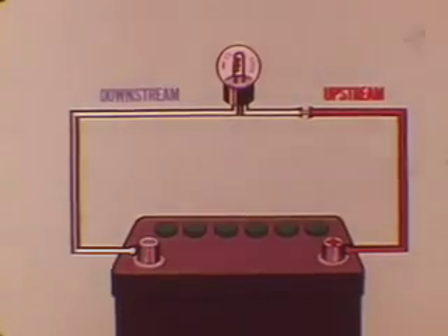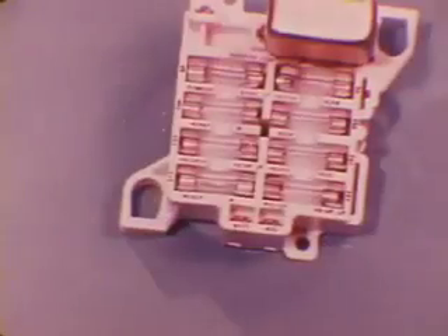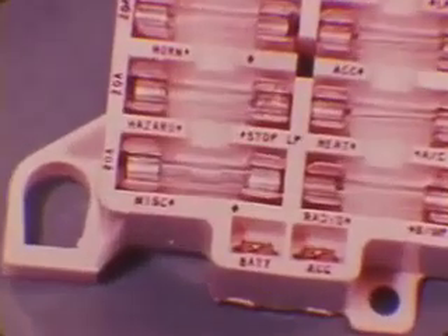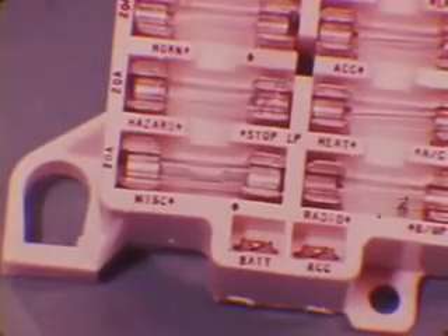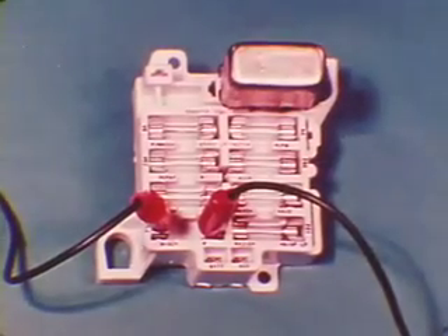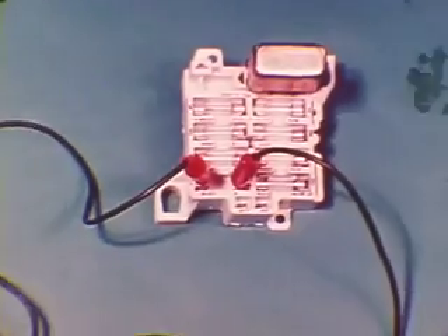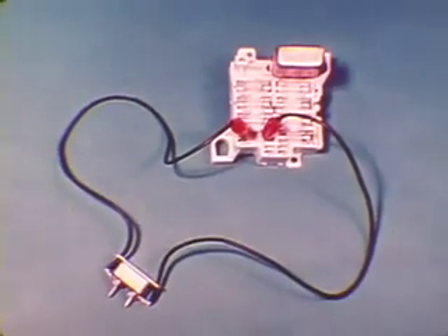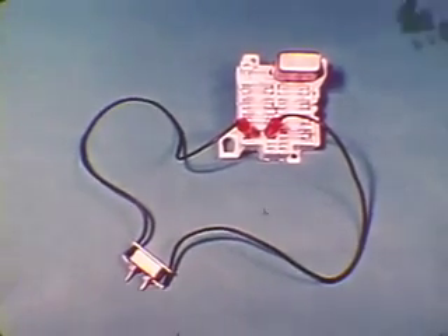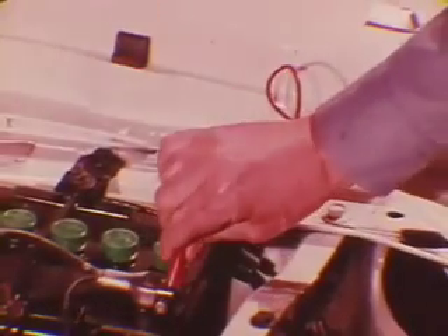Now back to our short problem. Checking out a short that keeps blowing a fuse is somewhat different from checking a circuit protected by a circuit breaker. If a new fuse blows after disconnecting the unit, the trouble is in the wiring. The trick here is to supply voltage to the circuit without blowing the fuse or burning up the wiring. You can do this by substituting a cycling type circuit breaker in place of the fuse. Then, use your test light the same way you would in troubleshooting a circuit normally protected by a circuit breaker.